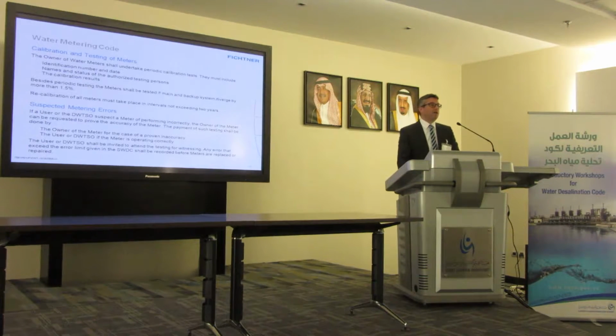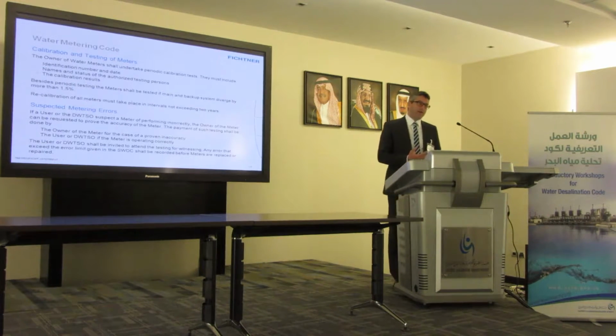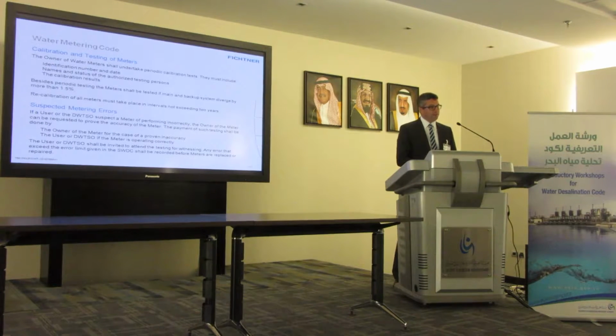Important point is that these meters are getting calibrated and tested frequently from time to time in order to know that the data gathered from these are correct. And such testing and calibration must include the identification number of the equipment, of the meter, as well as the name, the status of the authorized testing party, and of course the calibration results. In any case, the meters shall be tested when both meters, backup and main, are deviating by 1.5%, and in any case, at the latest after a period of 2 years.